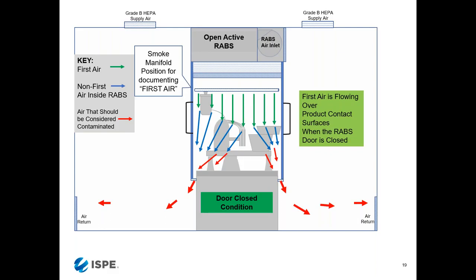It's common, and this is all design and integration issues. During dynamic studies this happens because now you're opening the door, and the air velocity inside could be lower while the one outside is higher, or you could have inlet issues. We just recently saw a company that decided they would have return ducts only on one wall. What do you think happened? Horrible turbulence as soon as you open the door, because the air where there were no return ducts was going directly into the RABS, since there was nothing else pulling it. So it depends on a lot of things: the placement of your HEPAs, the placement of the returns, the velocity in the enclosure, the velocity outside, and so on.